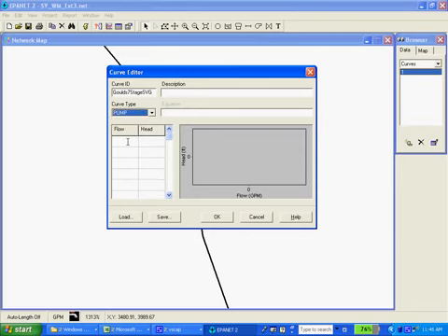So I'm just going to go ahead and start entering the pump curve, and this is using information straight from a manufacturer's literature of the pump curve, starting with 0, the static pumping rate. The head for this particular pump is 318 feet, and keep in mind that we selected with this model to use gallons per minute and feet for our units, although it doesn't actually display them here.